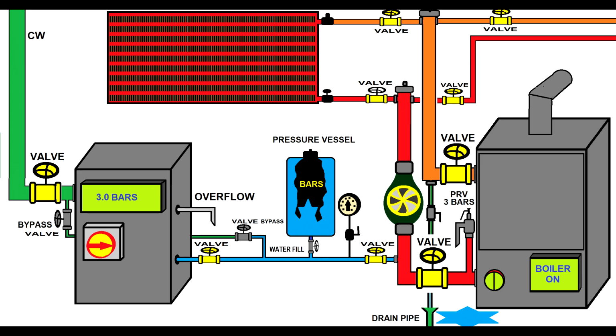Enough water will go out until the pressure stabilizes just below the PRV maximum allowed pressure, and then the PRV will stop. That's why when you turn up to the premises too late, you will only see the water on the floor, you won't see the PRV leaking.